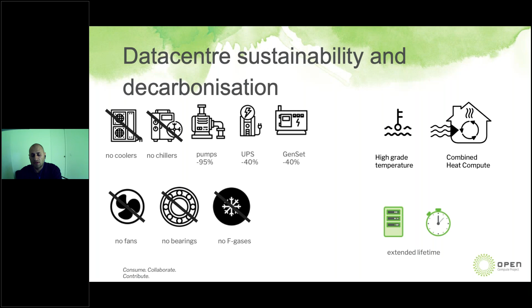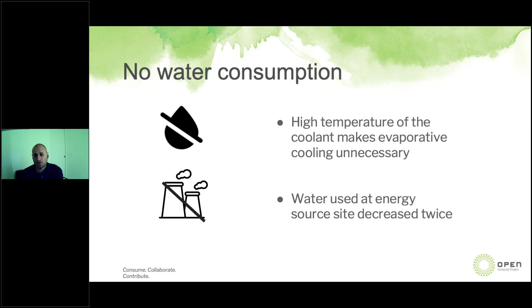Servers are safe as brand new, and lifetime is extended up to 10 years. Dry coolers are sufficient if the ambient dry bulb temperature is below 45 degrees Celsius, and so evaporative cooling generally is not needed. On the other hand, the whole immersion data center power input is lower than the conventional IT load, which makes sense for the global power grid.